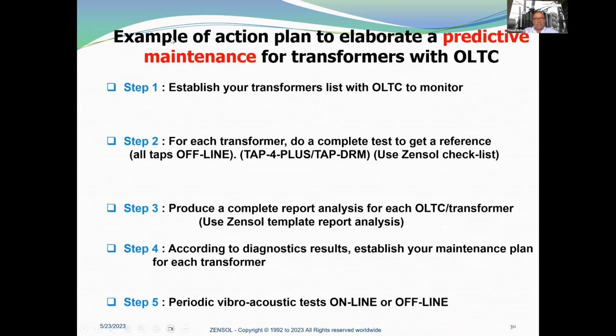So this is what we recommend: an example of an action plan to elaborate a predictive maintenance for transformers with OLTC. Step 1, establish your list of transformers with the OLTC to monitor. Step 2, for each transformer, do a complete test to get a reference, all taps offline, with Tap 4+ and Tap DRM, and we have developed a Zensol checklist. Step 3, we produce a complete analysis report for each tap changer with the transformer. We have also developed a Zensol template for the analysis report.